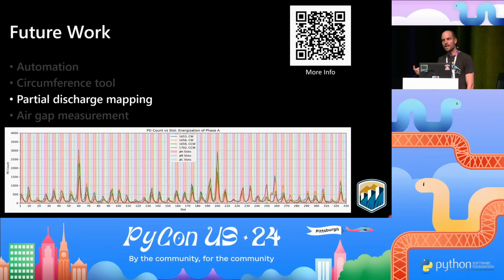So I discovered that using the NFC antenna found in your common phone can detect this signal across the air gap of the machine. So I slap that NFC antenna on one of the rotor poles, and I measure partial discharge, and I can say, hey, look at around slot 200. The stator has copper, iron, copper, iron, copper, iron to make that copper winding. And so it's slots. Every copper is called a slot. And so around slot 200 and around slot 60, I have high PD count. I can trend that. Is it increasing? Is it staying the same? And I can advise asset managers, hey, you can do a local repair or you need to do a bulk repair. And that's millions of dollars or thousands of dollars, right? And outage times as well.